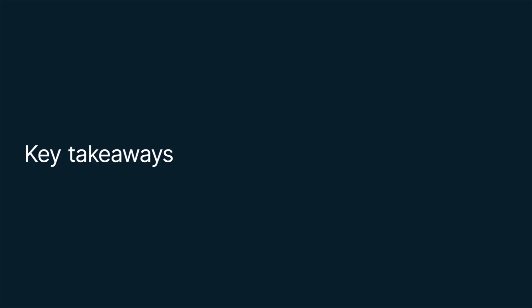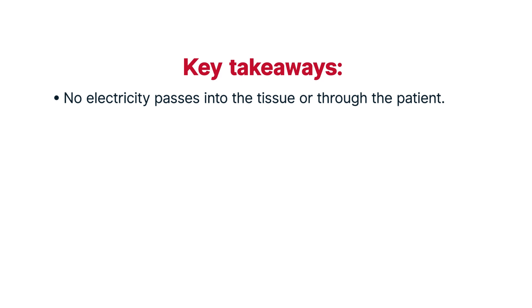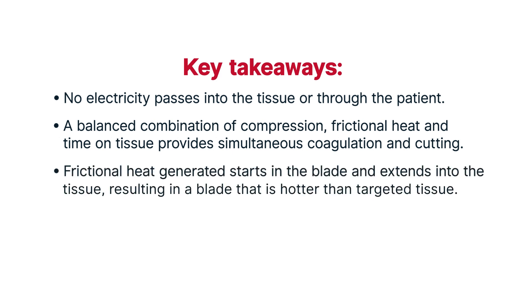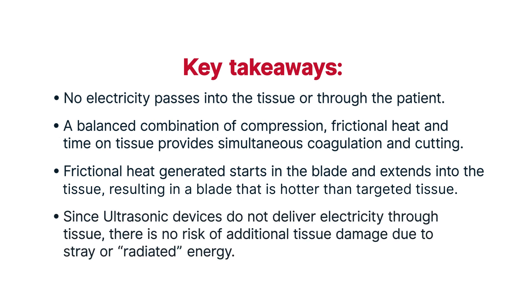Key takeaways. No electricity passes into the tissue or through the patient. A balanced combination of compression, frictional heat, and time on tissue provides simultaneous coagulation and cutting. The frictional heat generated starts in the blade and extends into the tissue, resulting in a blade that is hotter than the targeted tissue. Since ultrasonic devices do not deliver electricity through tissue, there is no risk of additional tissue damage due to stray or radiated energy.